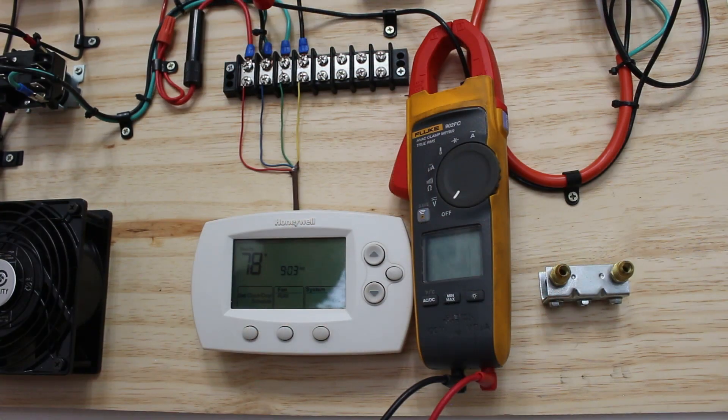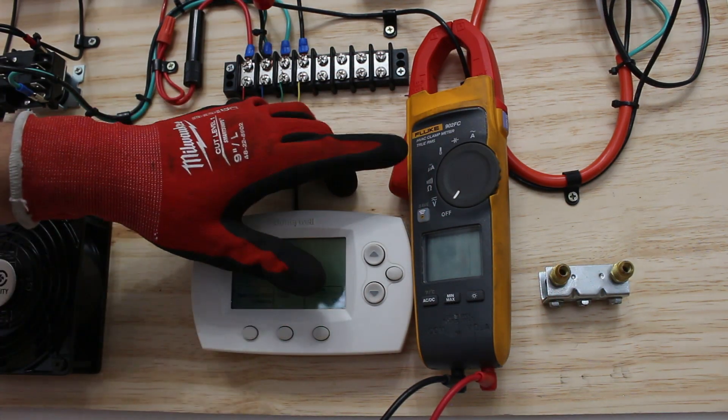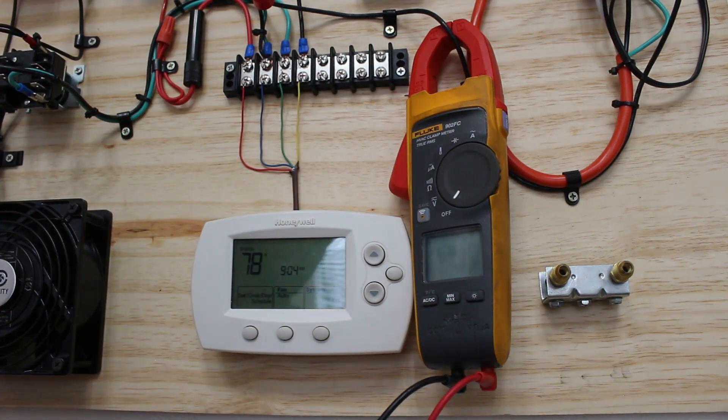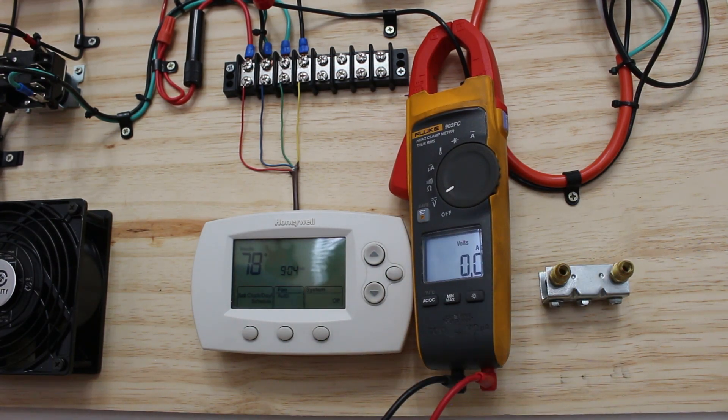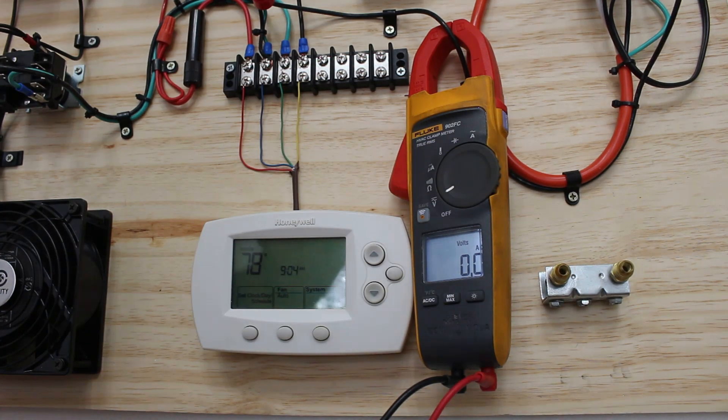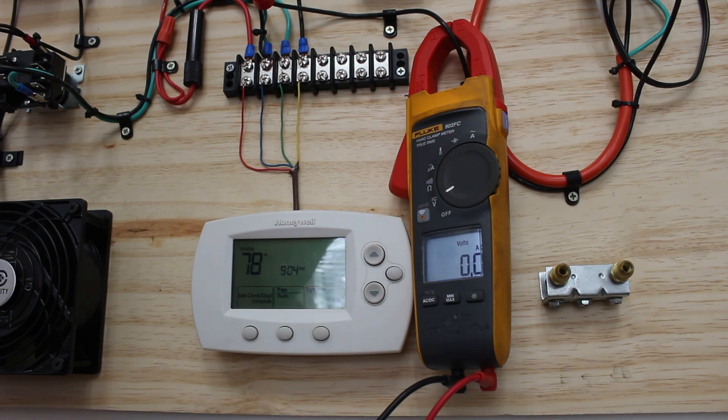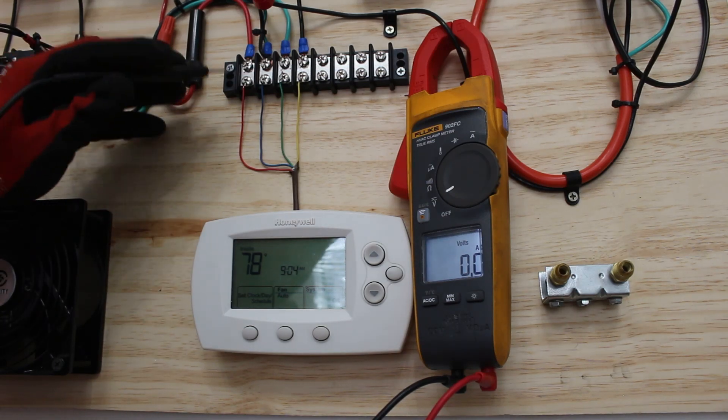The meter I am using today is the Fluke 902 FC HVAC clamp meter. We're going to set our meter to volts AC. Right now we have the thermostat in the off position. Nothing should be happening but since we have power applied between terminal R and C we should have 24 volts. So this is R and this is C.